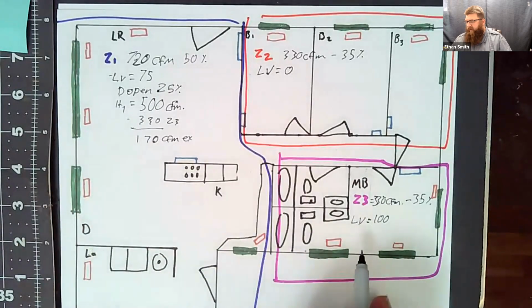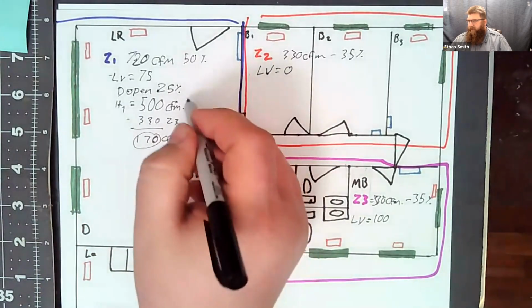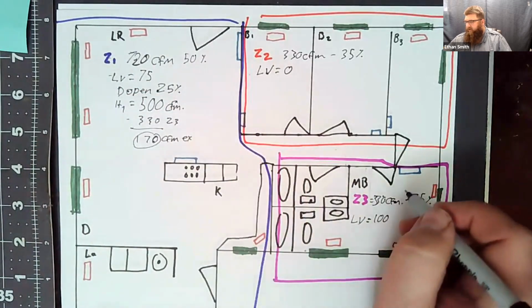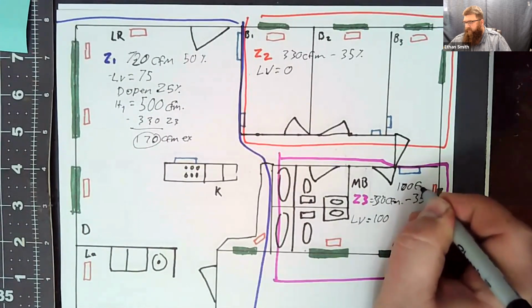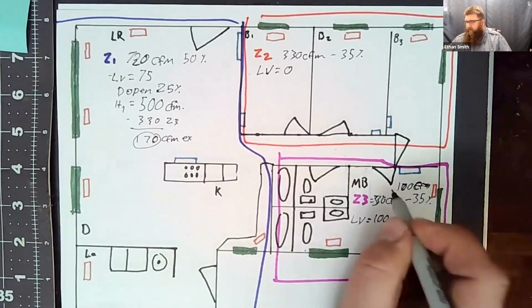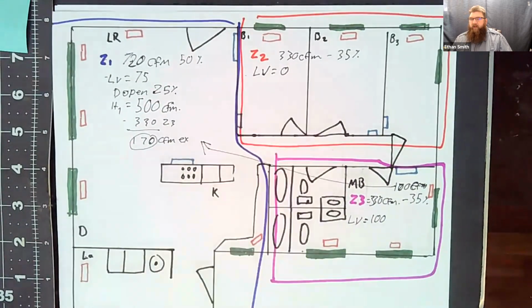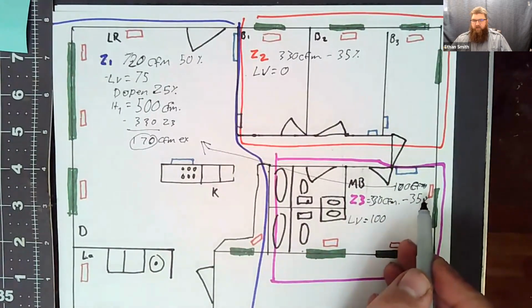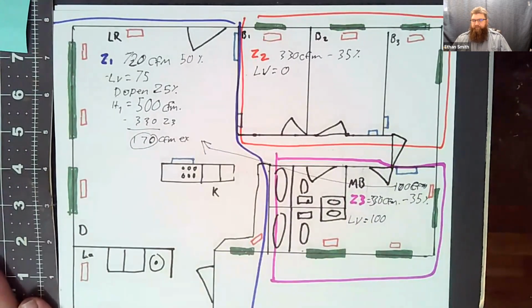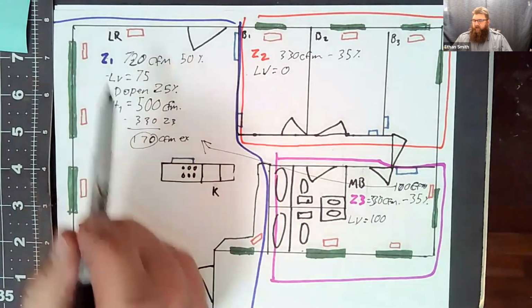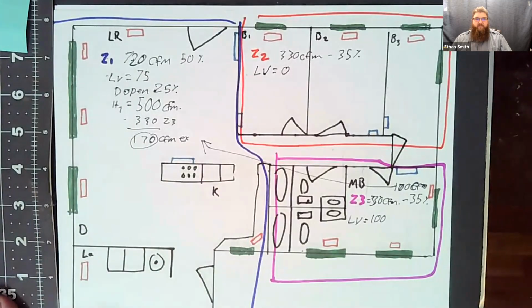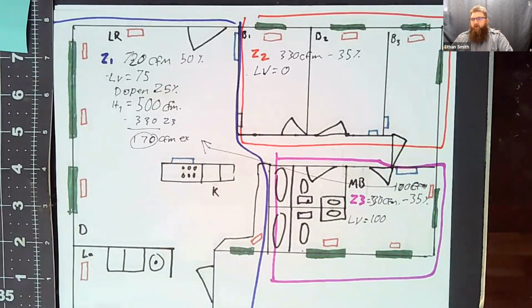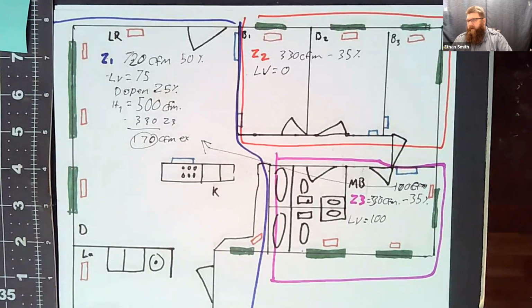Okay, which will then take my extra 170 CFM and put it into zone 1. So we take my 170 and we're able to relieve it into zone 1. So now we're taking that excess air that would just be wasted energy with any other relief strategy, and we're putting it where it's going to be useful. Obviously, 170 CFM in a 720 CFM zone is a drop in the bucket. Okay. It's not going to do a ton to influence the zone. It will do a little bit. But at the same time, we're not wasting that energy that we've paid for.